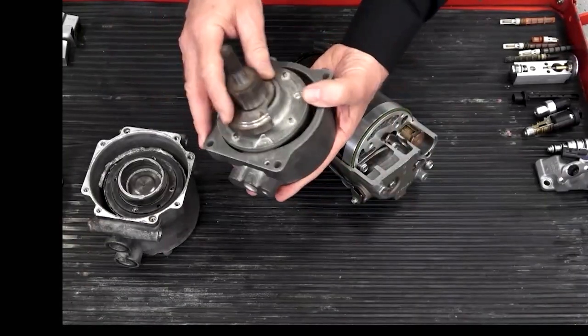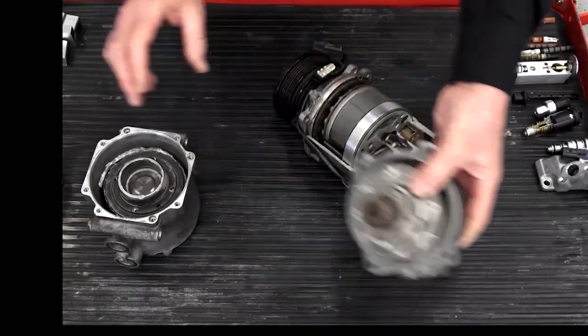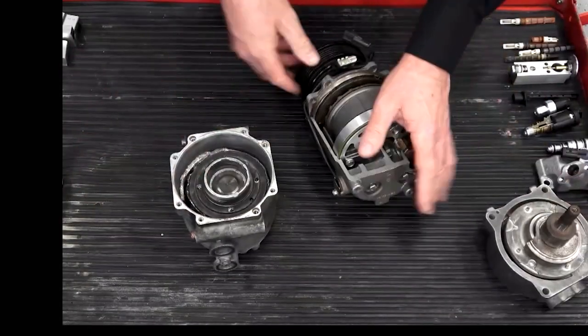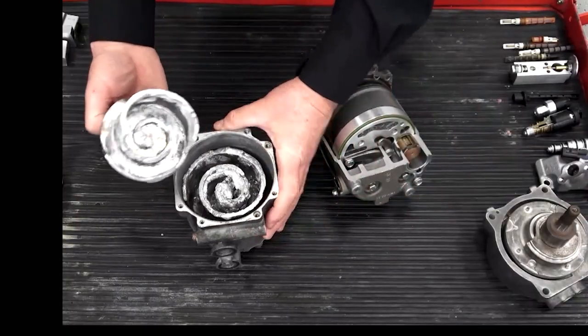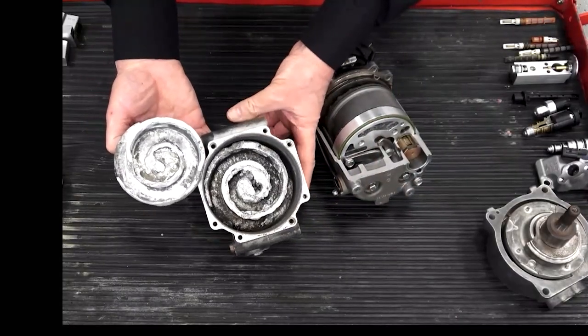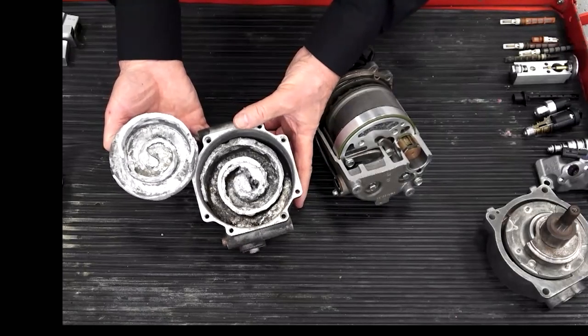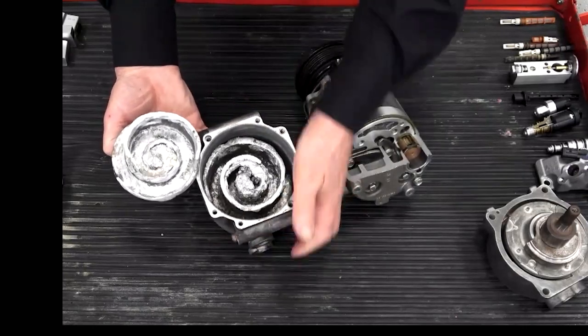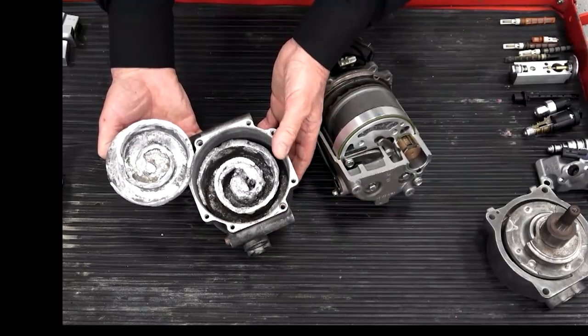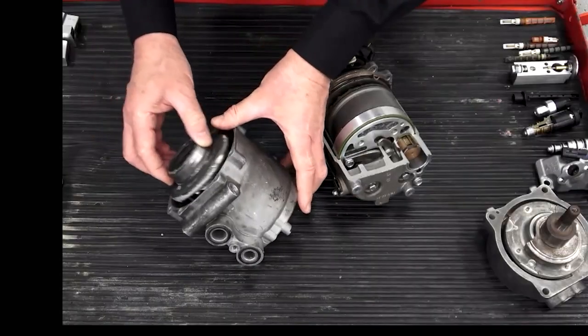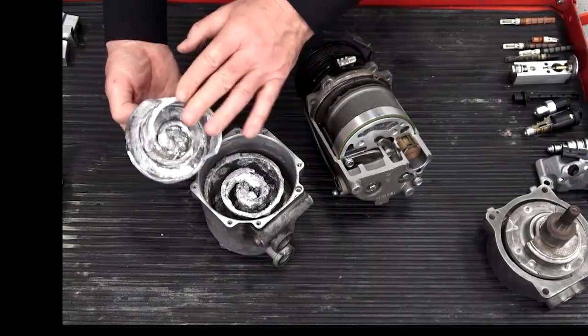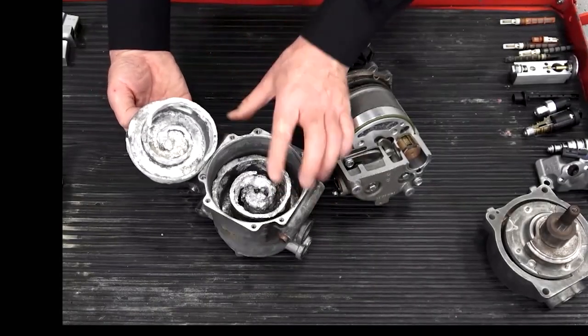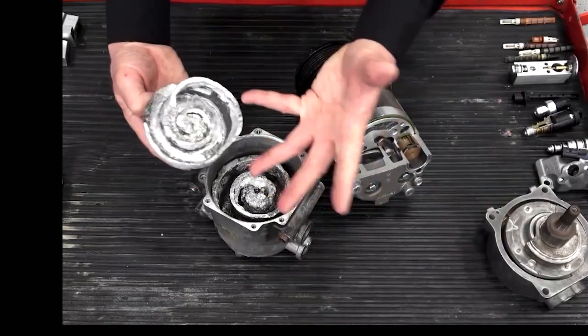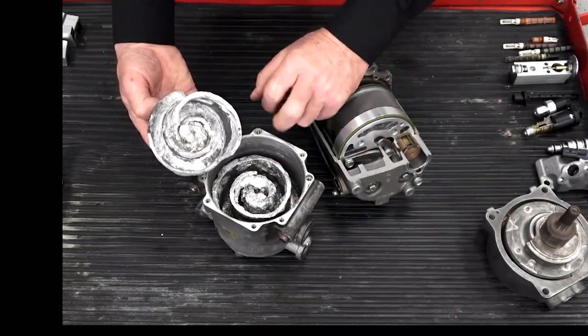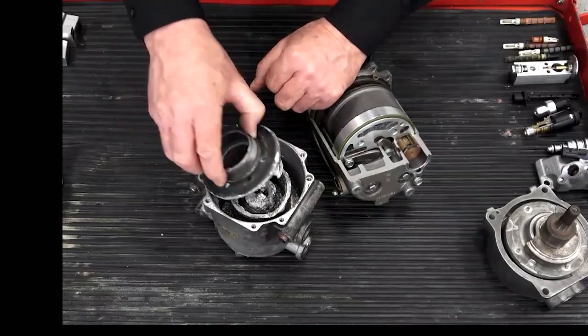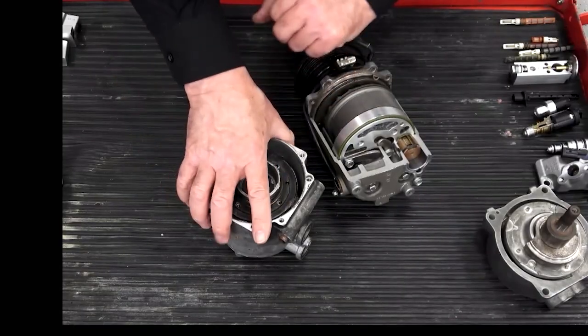They're a delicate design. And just to illustrate that point, here is a classic example of a scroll compressor that was assembled when the system was put back together with improper lubrication, not properly lubricated. Just by looking at it here, you get a very clear sense of the amount of junk and debris that can be generated in a system like this when the compressor fails. So that's a big problem with scroll compressors.